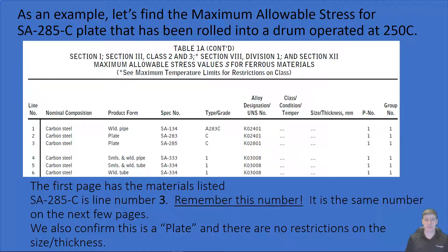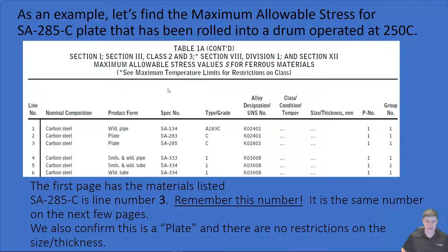Let's make use of the chart. Let's say, for example, that we want to find material SA285C. It's been rolled into a drum from a plate and it's at 250°C. We want to find the maximum allowable stress because we're going to need that for some calculations. We go to the first page of those groupings of four and we find a list of all our different materials, with different specs and grade types filling the page.